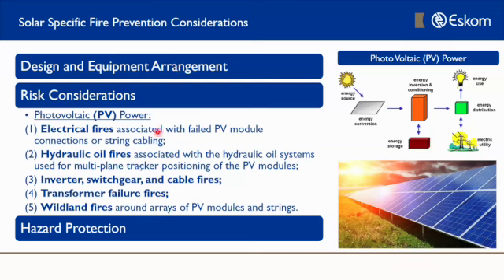Solar-specific fire prevention: design and equipment arrangement are very important aspects to consider, along with hazard protection — whatever hazards we define, how do we protect against them? For PV specifically, I want to highlight electrical fires related to failed PV modules or strings and cabling, hydraulic fires from hydraulic oil systems used in multi-plane tracker positioning, inverters, switchgear, cable fires, transformer failures, and external risks — the exposure to fires around our plant that could affect our system. These are typical risk considerations for PV.